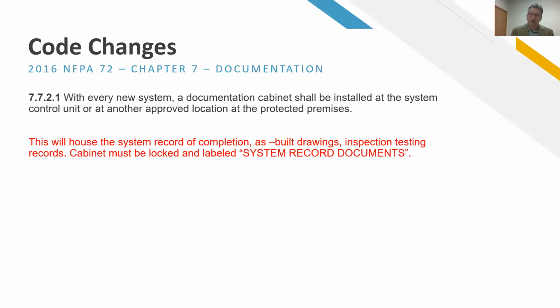So pretty self-explanatory there, and this is required in new applications. There's nothing stopping you from ordering a document box with someone's logo on it, with a jump drive. If you want to avoid the curled up yellow papers behind the electrical conduit coming down into the panel, this is the way to do it. It's actually required per code for new installations.